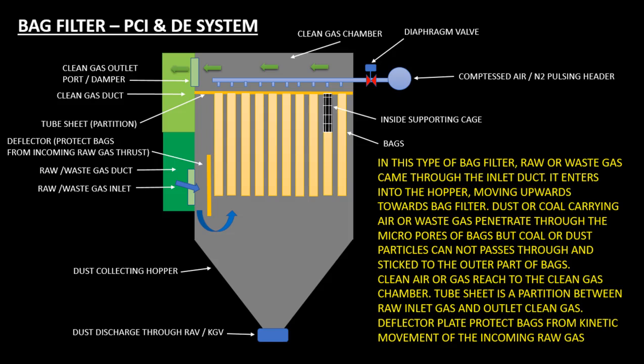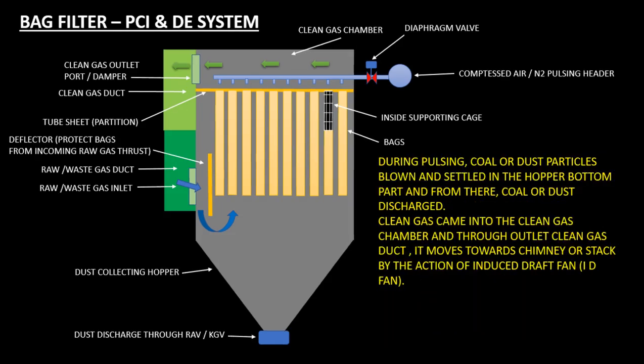The tube sheet is a partition between the raw inlet gas and the outlet clean gas. A deflector plate protects bags from the kinetic movement of incoming raw gas. During bag cleaning or pulsing, coal or dust particles are blown off and settle in the hopper bottom, from where the coal or dust is discharged.